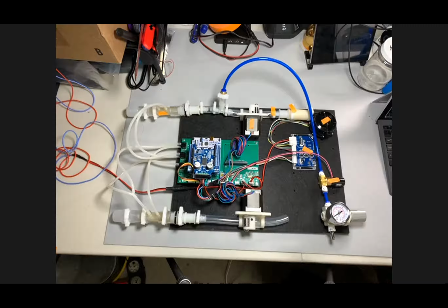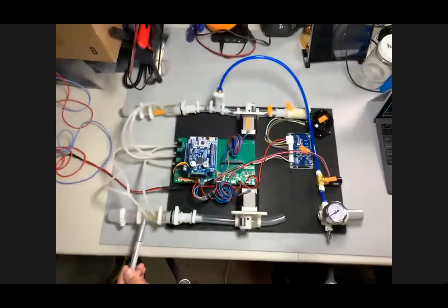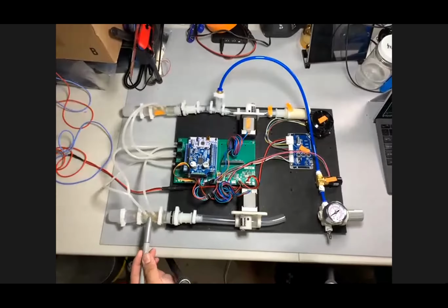So we can leave that outside the ventilator, but it's just good to know that it's there. So returning from the patient, the exhaled air will come here through another one of these patient fittings, through, again, the 3/4 inner diameter tubing, which is clamped, and coming here to another one of these venturis. This venturi is identical to the other one, as it will see essentially the same flows going in and out of the patient. This is being measured again by these differential pressure sensors on the circuit board.